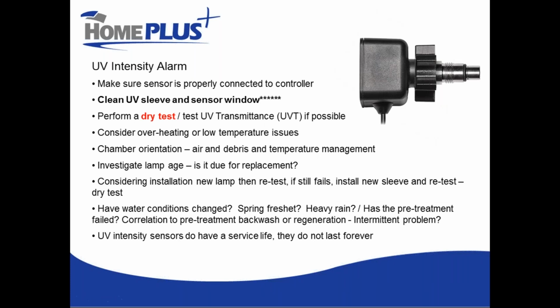Okay. So the number one problem that we hear about in troubleshooting related to UV systems is related to alarms. I have an alarm where my system has shut down. Often a solenoid has closed and won't let me produce any water or send any water out to distribution because the system is saying that it cannot adequately or safely disinfect the water. What do I do? Where do I go? And there's a couple of things that you can do that are quite definitive in eliminating some of the possibilities.